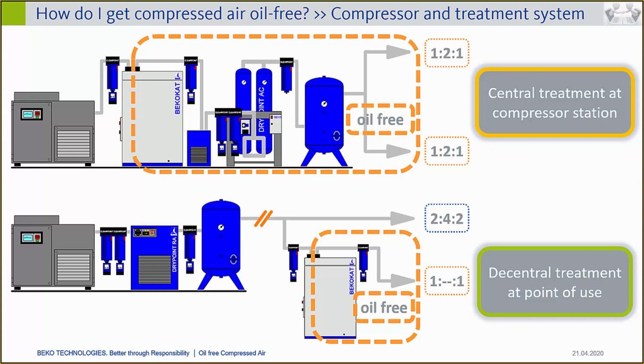I mean, the OCV would be the best option in that case, and in the shortest period of time it will give you information on what happens and when the lifetime of the catalyst is exceeded. And if you do not have this OCV, the only chance is to take samples regularly and send them to a laboratory and wait until you get the numbers.